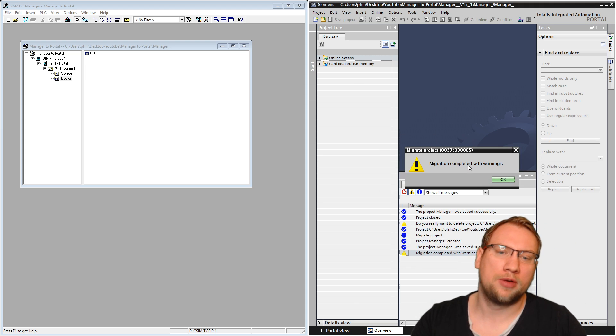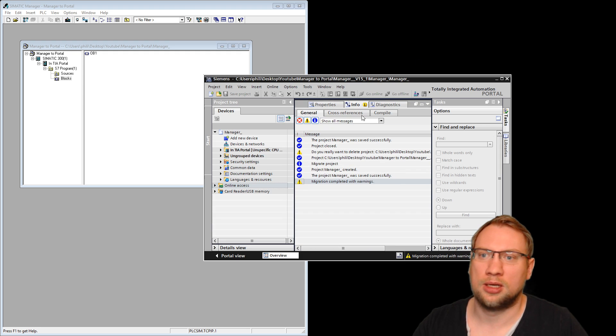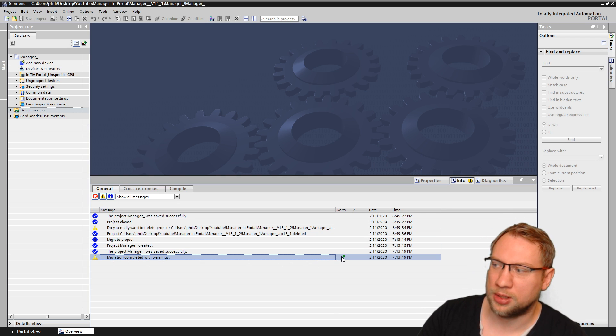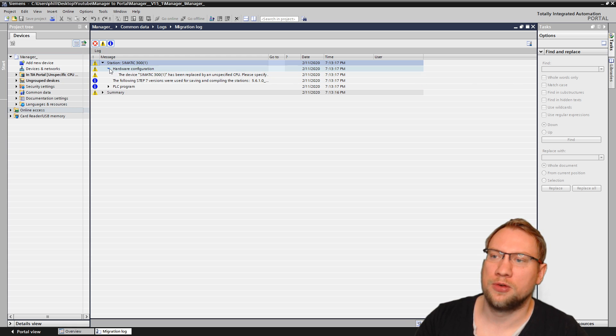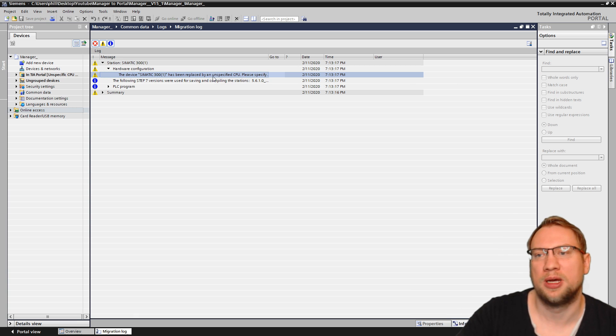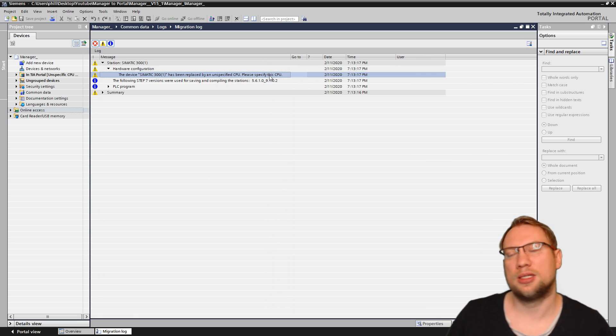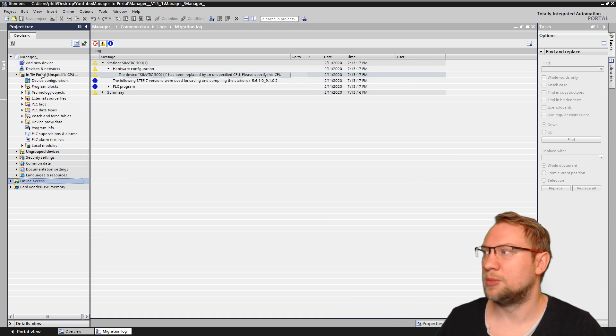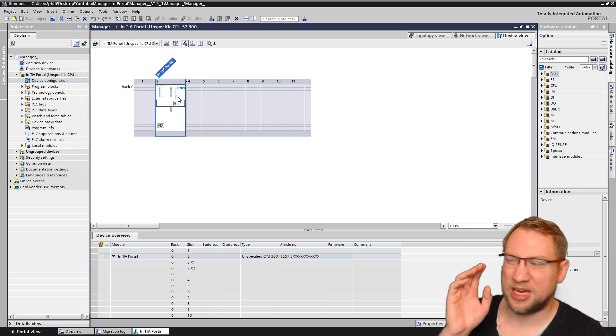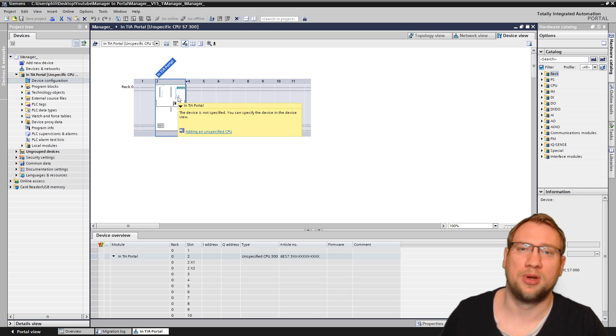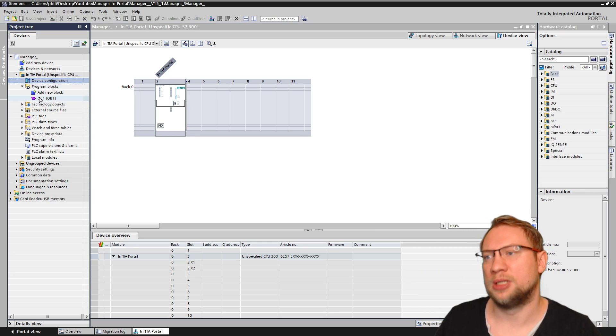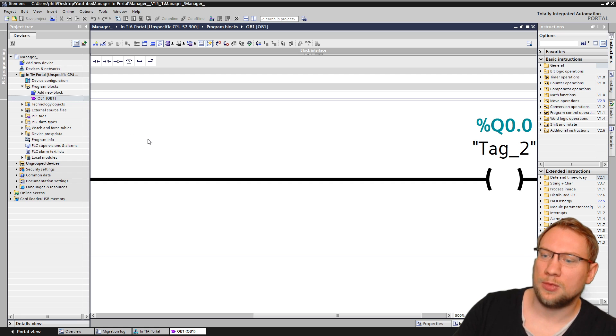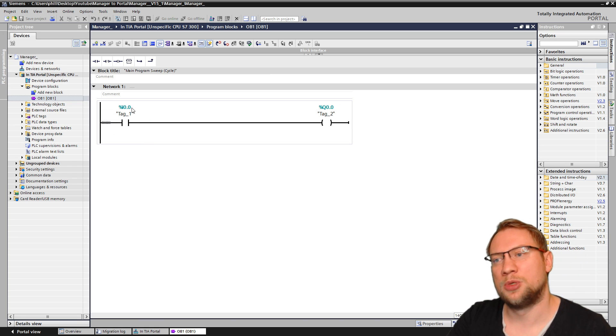The migration might take some time depending on your program and how much hardware you have. Migration completed with warnings. Let's expand TIA Portal. The warning says: 'Hardware configuration: the device SIMATIC 300 has been replaced by an unspecified CPU — please specify this CPU.' This happened because I left the hardware configuration checkbox unchecked. If I go to device configuration on the left side, I have just the blueprint of an S7-300 and would now need to choose the correct hardware. Let's first check the program.